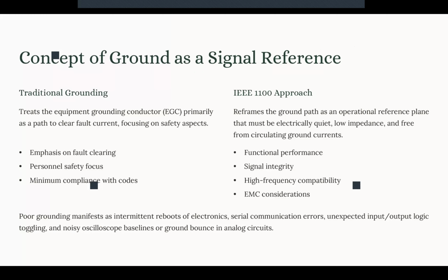Now, we said that the traditional grounding system is a safety-oriented kind of system. So it focuses on fault clearing and personal safety. They are designed to carry fault current, and they are designed to do that temporarily, so it happens during the fault. The impedance value is designed based on the fault current magnitude, not signal stability. And when we talk about the safety ground, when they design it, they do not consider the high frequency transients. So they always set the impedances and the design for low frequency fault current.